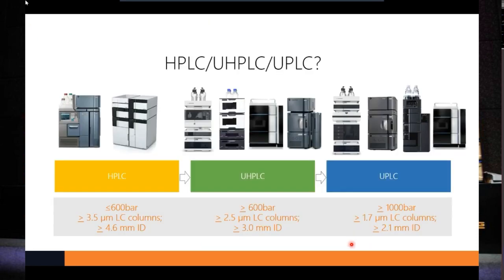And as the technology improved, HPLC can be divided into three classes. The main differences among the three systems are the maximum pressure tolerance and the size of the column used for analysis. For HPLC, the maximum pressure is usually below 600 bars or 60 megapascals. 40 megapascals is always a standard. And the particle size of the column silica is usually larger than 3 micrometers. Usually we use 3, 3.5 or 5 micrometers.